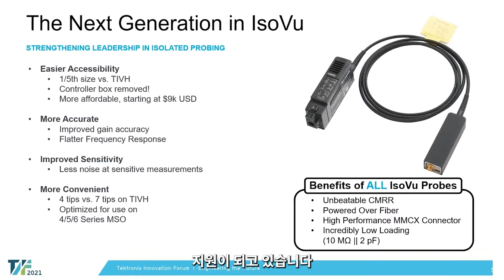Apart from just being able to reduce the overall size and mass of the probe, we've been able to improve the gain accuracy of the probe, and we've been able to achieve a flatter frequency response. So for those of you that were operating our Gen 1 probes towards the higher bandwidth range, we've been able to decrease some of the overshoot that was apparent on Generation 1 and really flatten it out with Generation 2. And then particularly at low volts per division settings, so say below 1 volt per division, we've been able to improve the noise sensitivity on our Generation 2. In addition to that, we'll talk about some of the tips and how that plays into the next slide. We've optimized this particular probe to be used on our newer generation scopes. So our 4, 5, and 6 series MSOs are the scopes that we currently have support for with our Generation 2 probe.